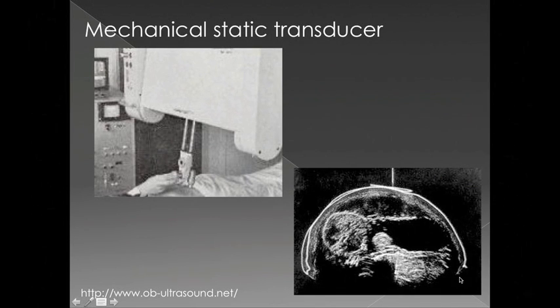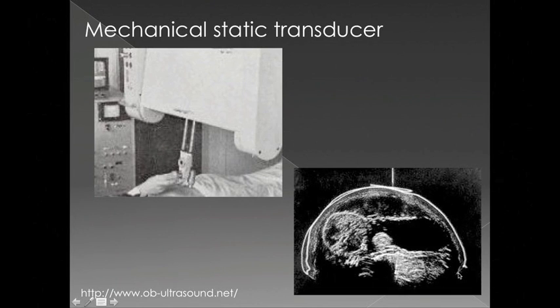One of the things that's neat about this image is it actually shows you that with the mechanical static transducers you actually had a much broader field of view than what you have with our current electrically steered transducers.